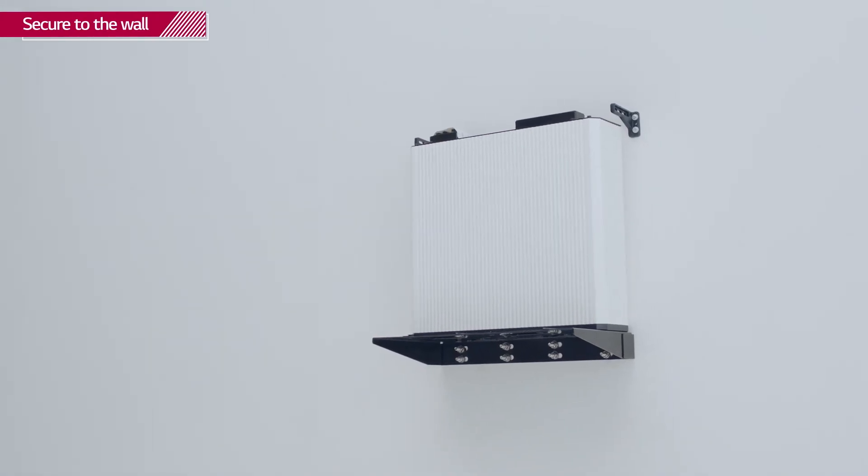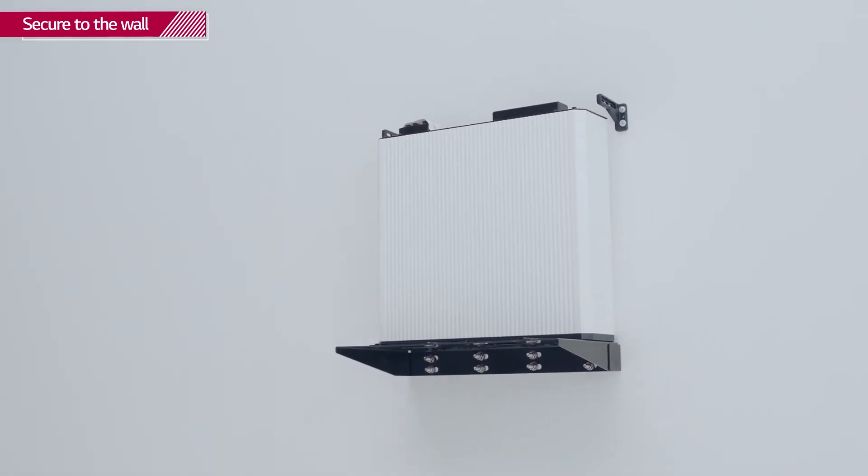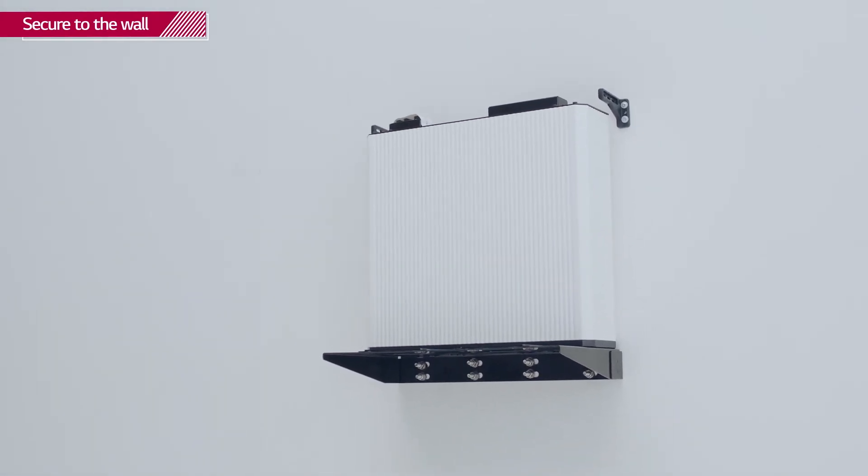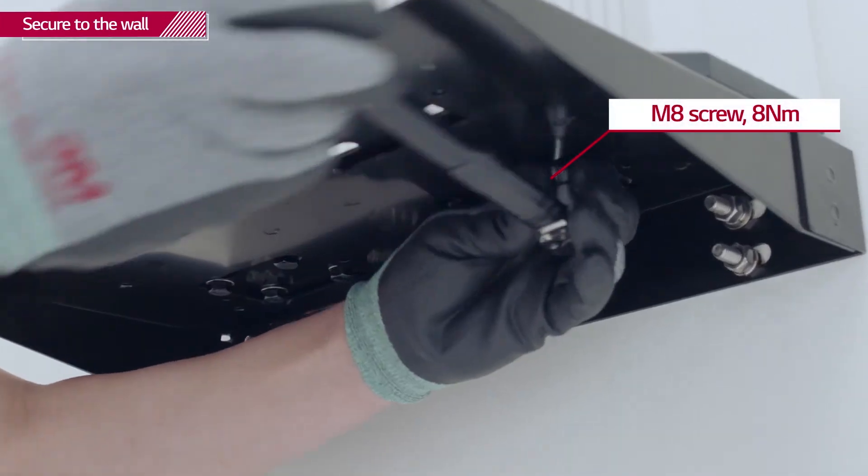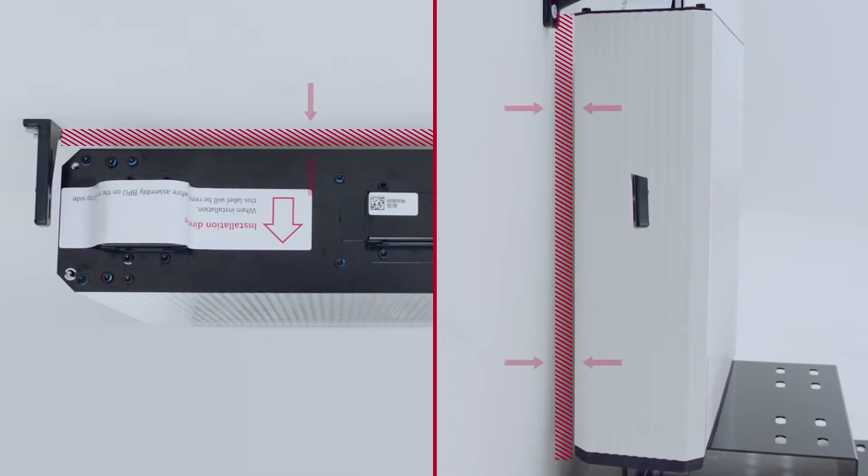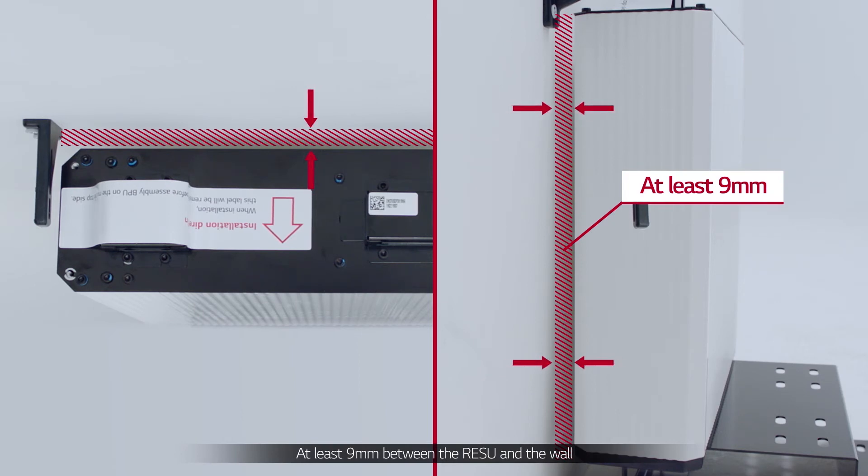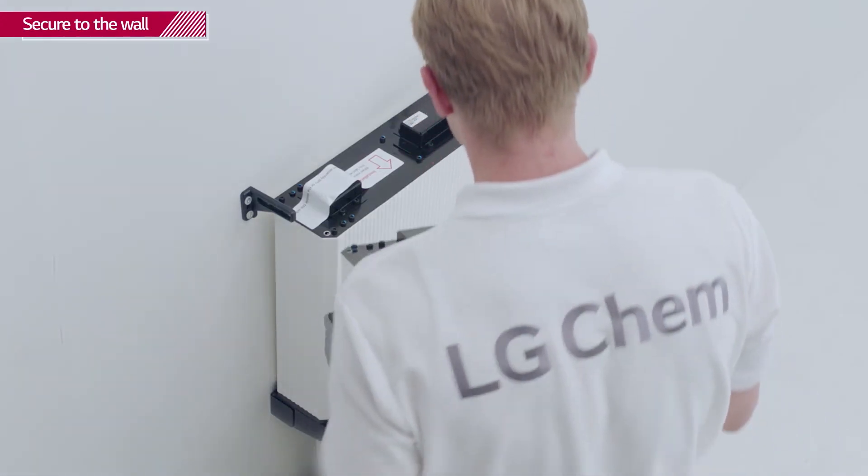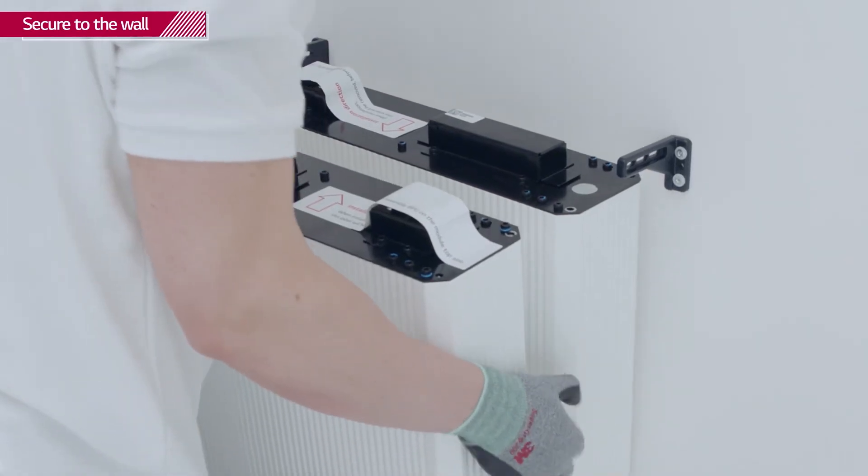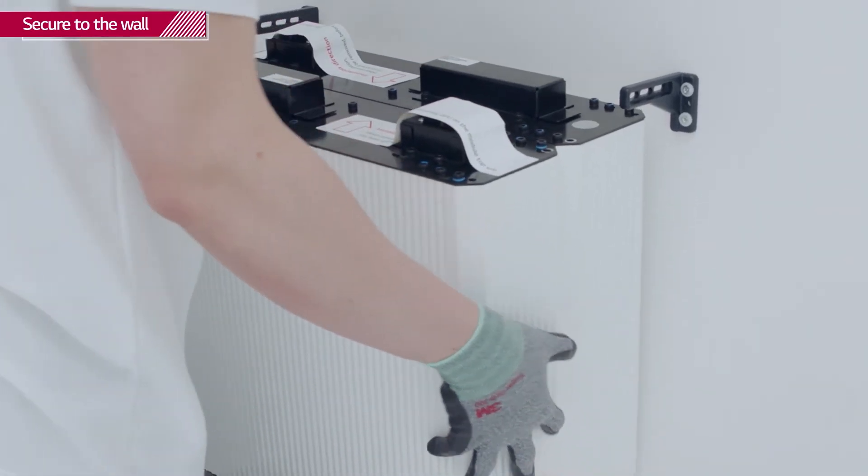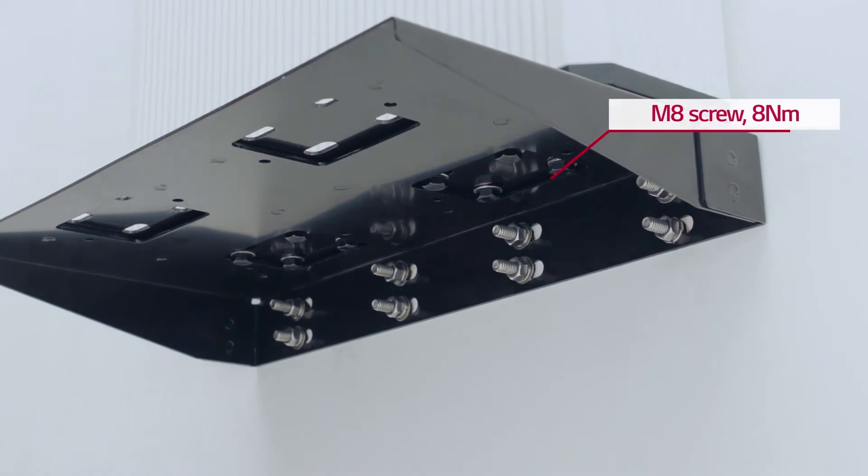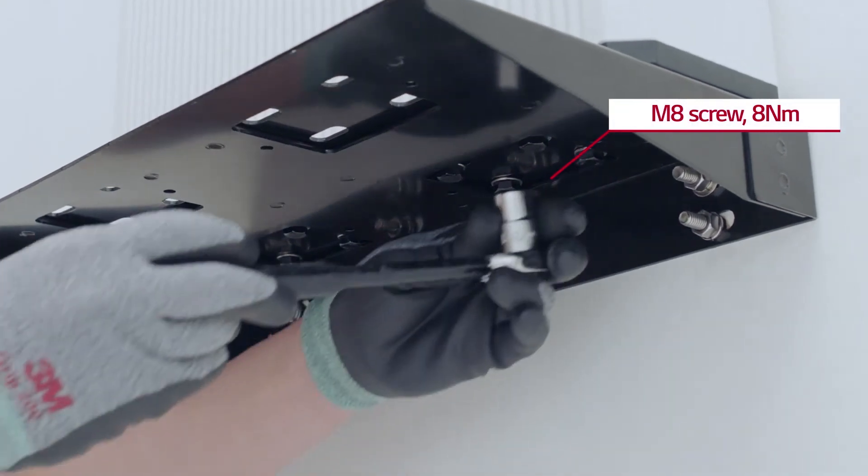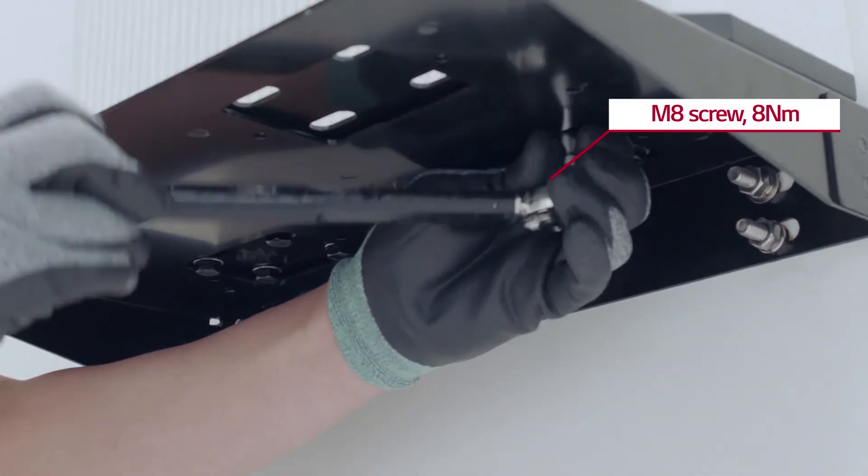Place the first battery module on the wall mounting bracket and fasten with eight screws with a torque of 8 Nm. Install additional battery modules the same way.